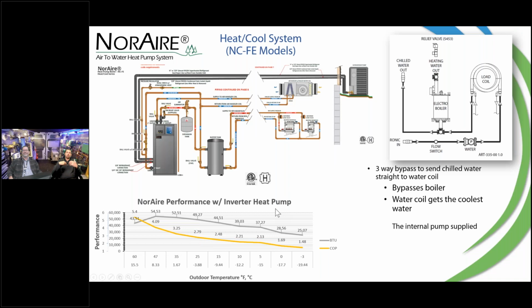But having that addition of the backup boiler—to that point, God forbid, and I said it before, redundancy, I love redundancy. God forbid something happened to that outdoor unit, right, and it can't do what it needed to do, or it failed, that kind of backup happens seamlessly. You don't even know it, but it's going to switch over to heat pump and go right to the electric. Internally, it sees the differential.